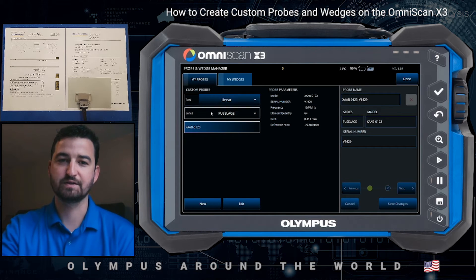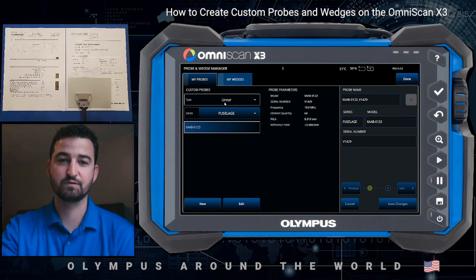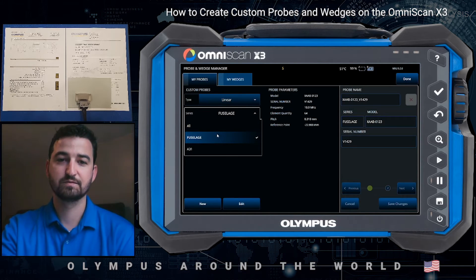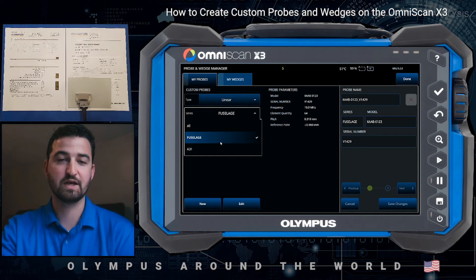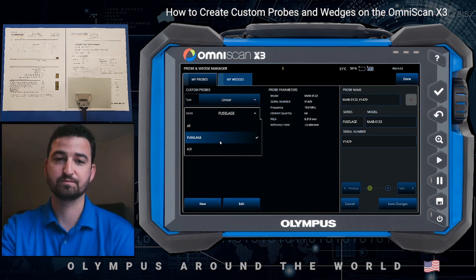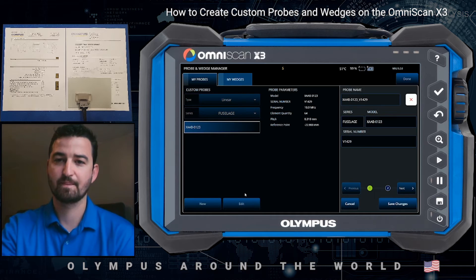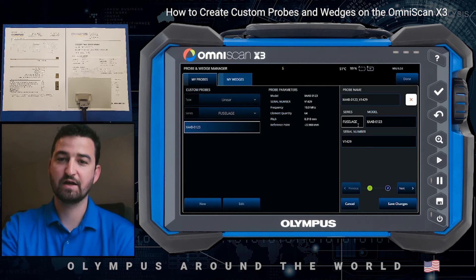Here you have type and series. Type is the type of array or transducer that you have — in this case we have a linear probe. The series can either be a standard series like A31 or A32 weld series probes, or we can do an identifiable series, in this case fuselage, to sort all the information that we would use for this inspection. You would typically start with new, but I'll go to edit to show you the steps. We use the identifiable fuselage as our series.